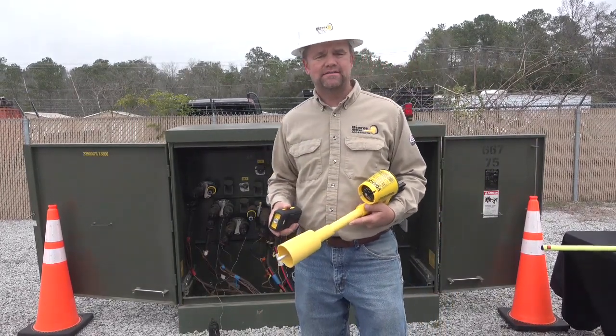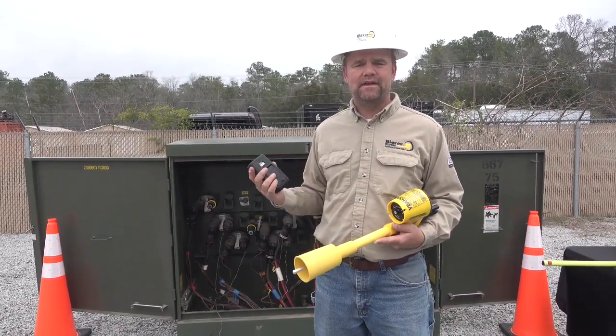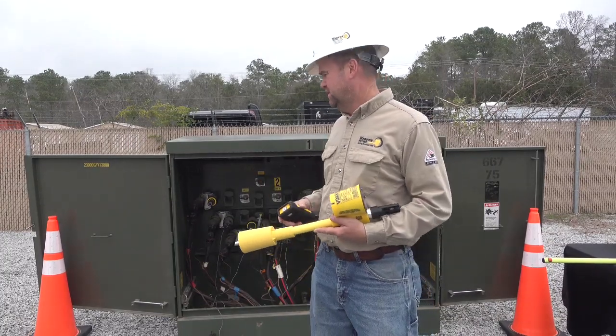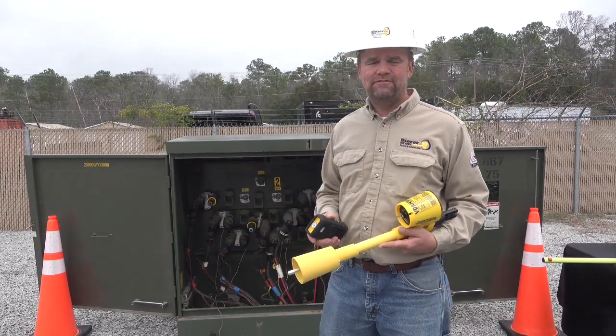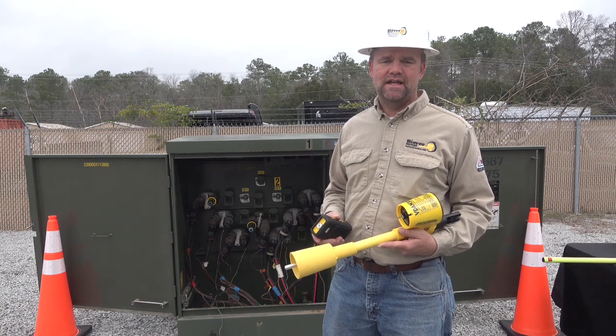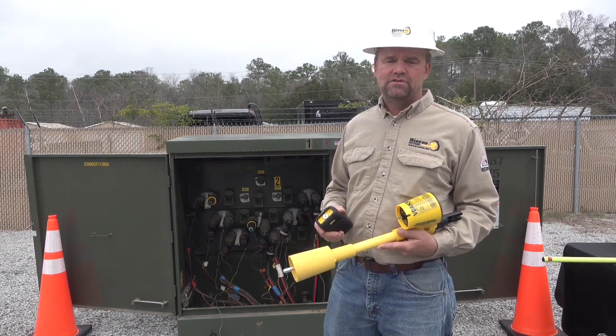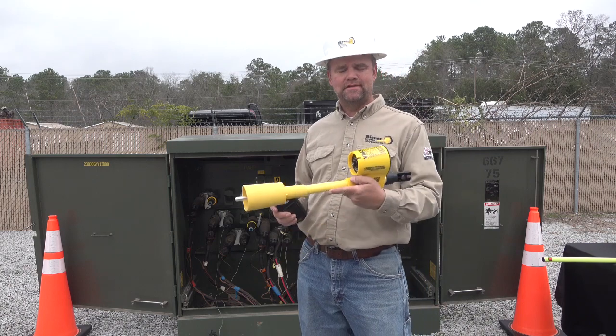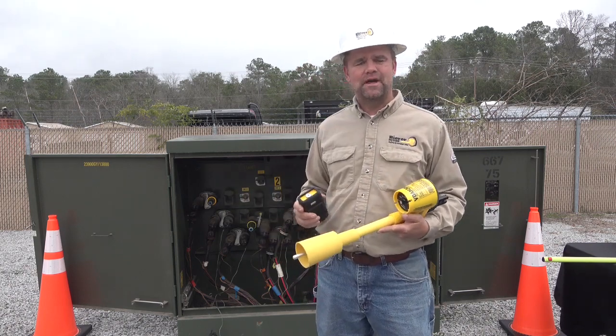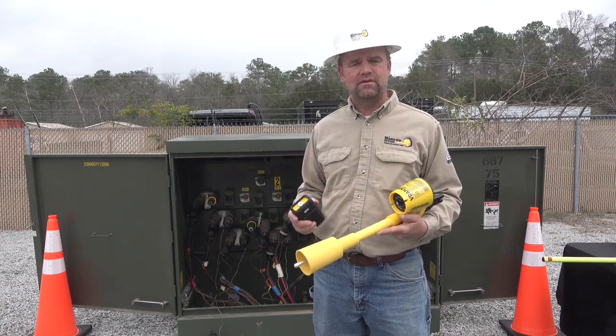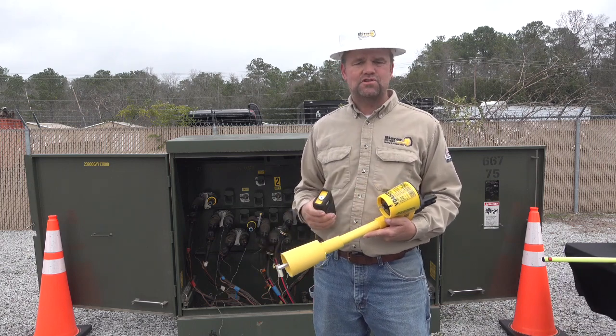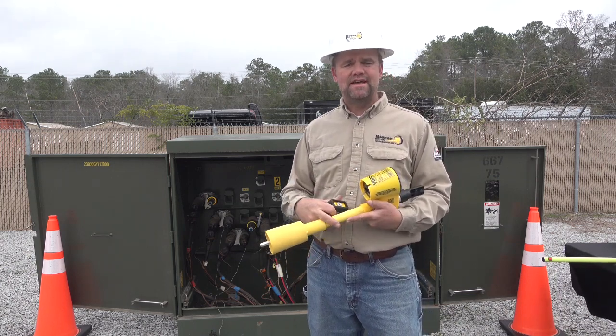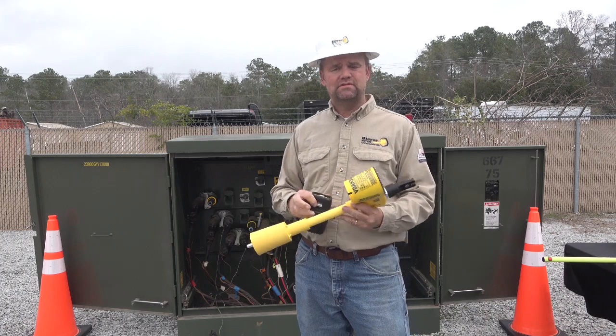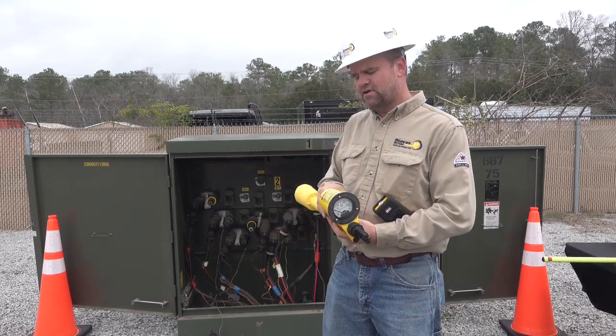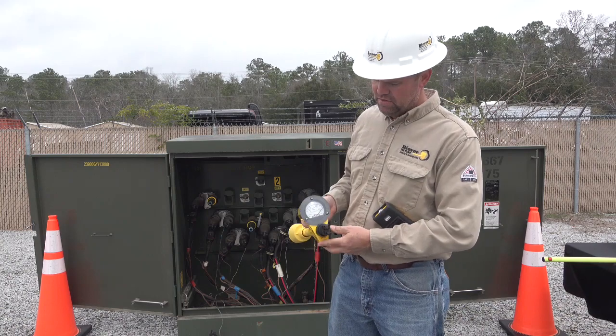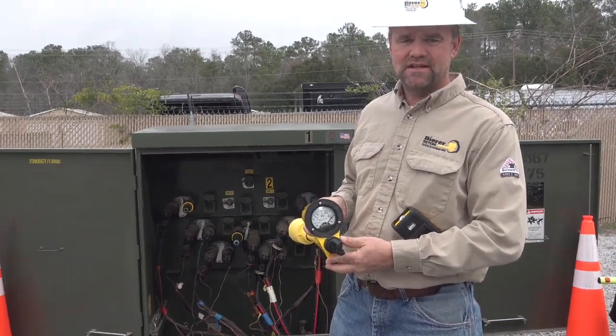All right, in our first demonstration, we're going to test for de-energized and energized. We have both situations behind me here in our pad mount transformer. This device is 13.8 phase to ground, so 13,800 volts phase to ground. So I should get some potential on my display, plus or minus about 30% as worst case scenario, using the VDAH300. And again, I want to test the device before and after each use. So I want to test it by turning it to the T position. I want to see a near full deflection on my scale.